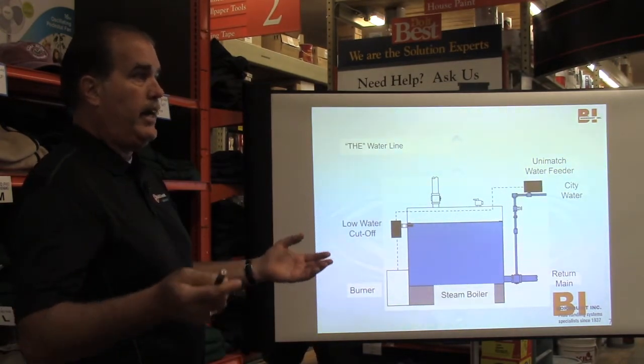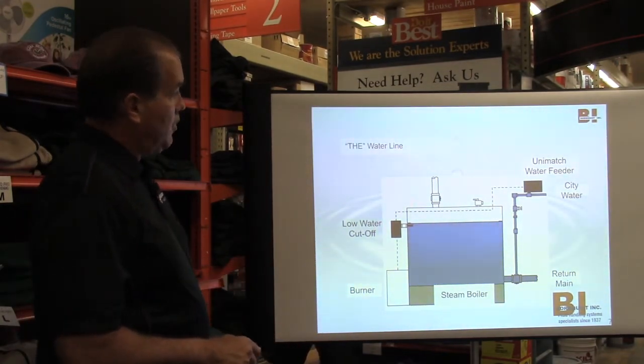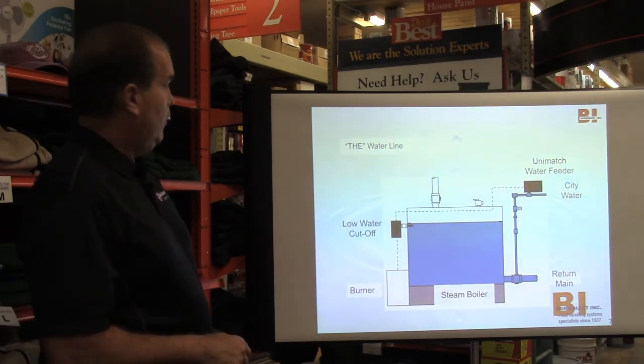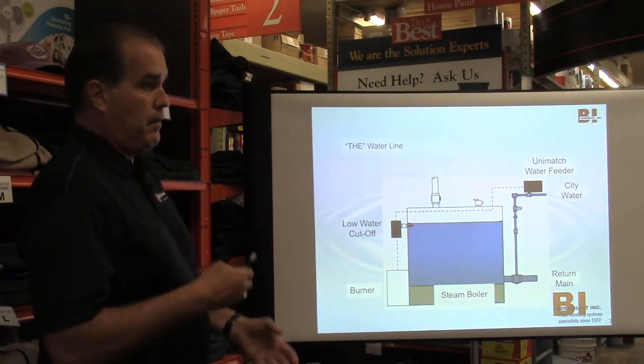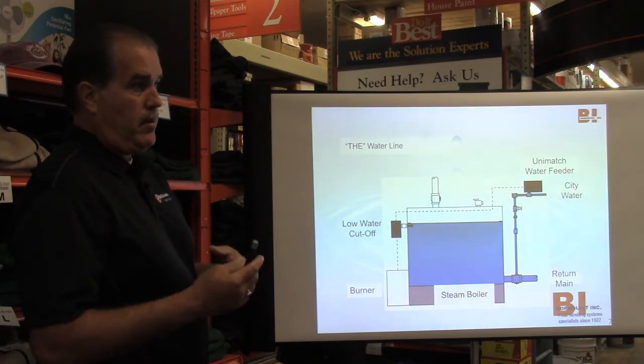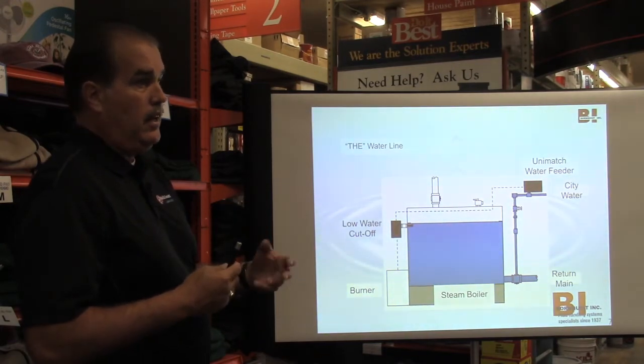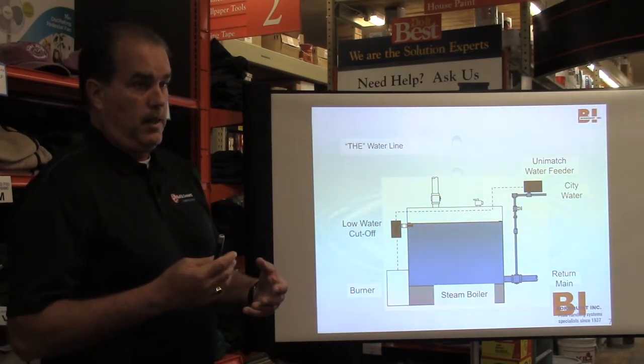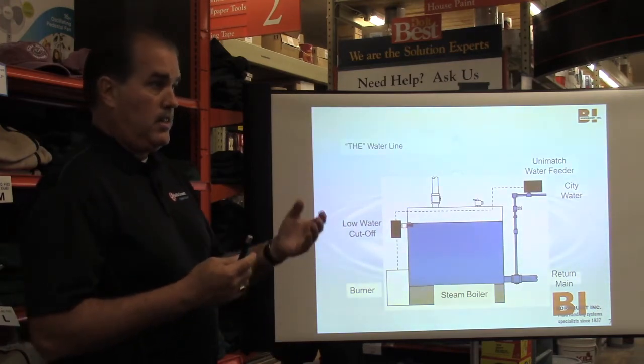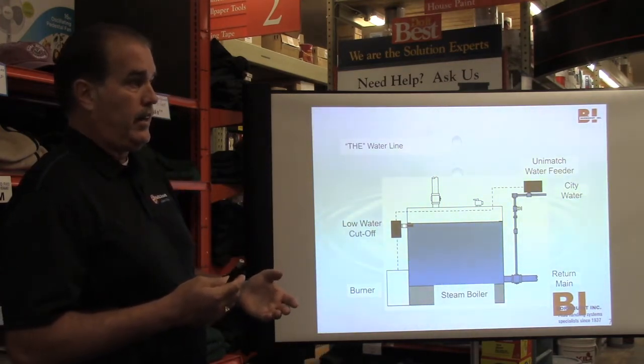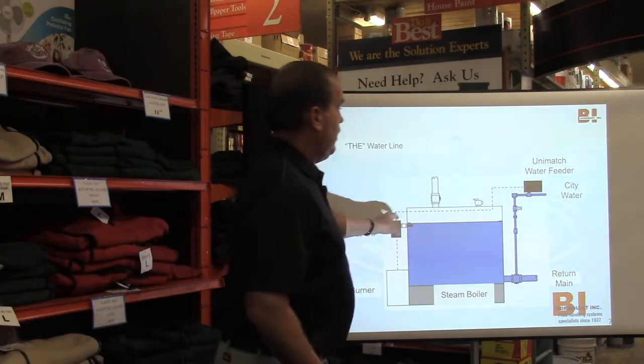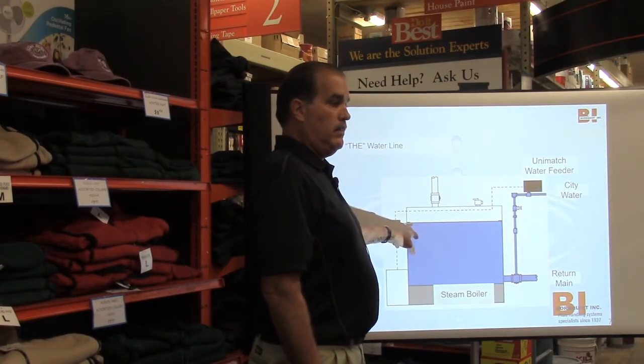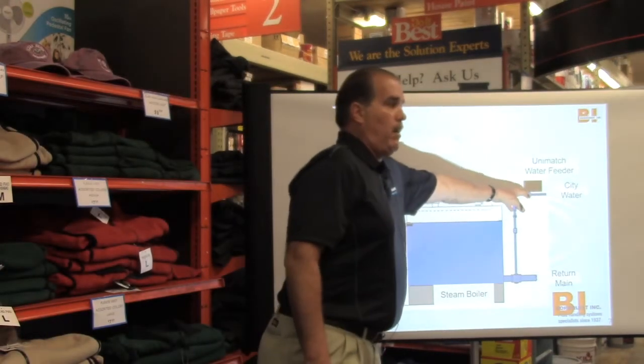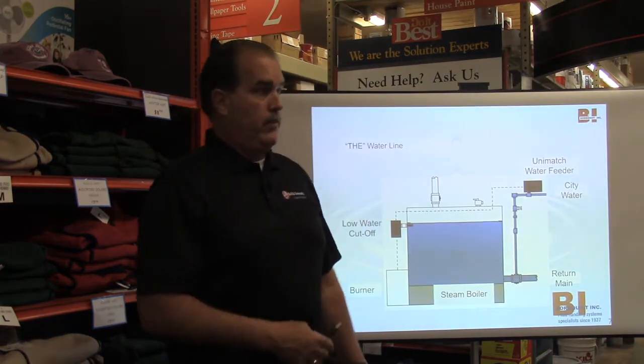But now you're like, well, I got no heat. Well, it's also wired to a water feeder. So when it shuts the burner off, there may be a time delay. Bear in mind, it's not going to happen instantaneously. Some of them are adjustable time delays, so they can actually change it. Typically, it's about 15 to 30 seconds before it says, okay, I truly am out of water. Now I'm going to turn my water feeder on and let water in from the city.